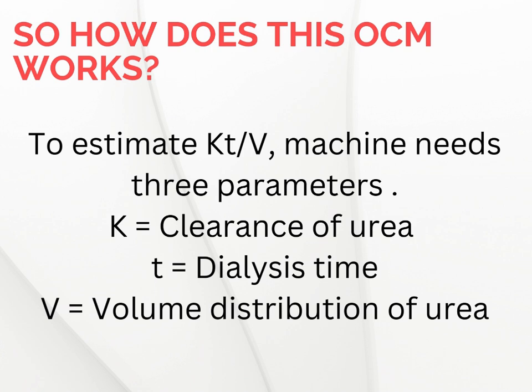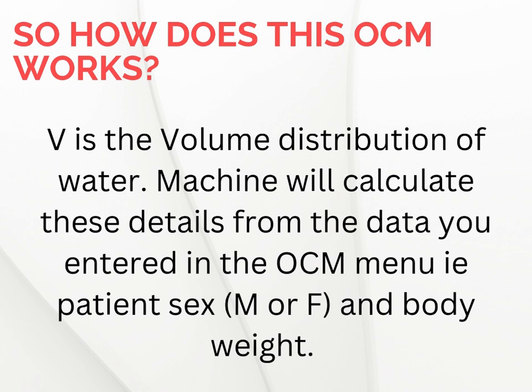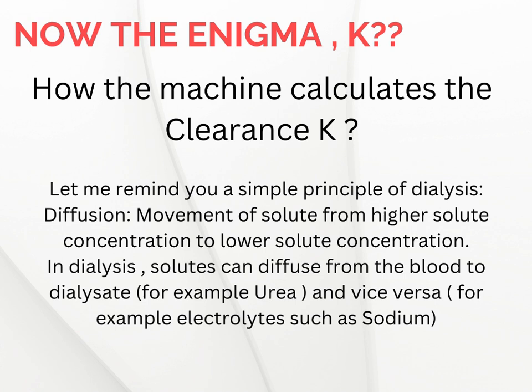So how does OCM work? OCM relies on three factors: clearance K, time T, and volume V. The machine automatically gets T because it's the one running the dialysis. Volume V is calculated from patient details like the patient's gender and weight. But the real enigma is how it calculates clearance K — let's unravel that mystery.